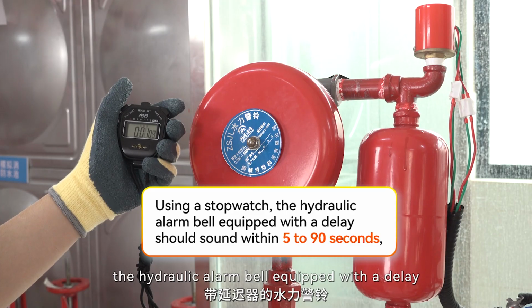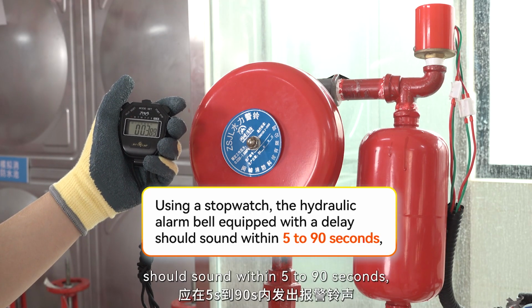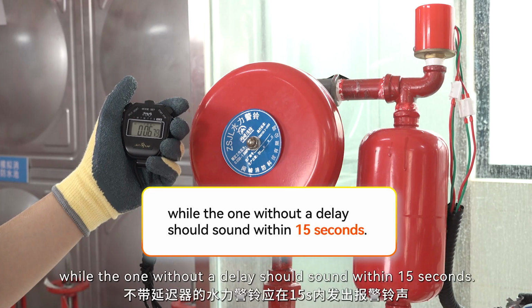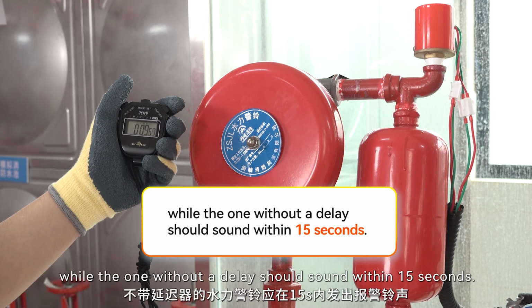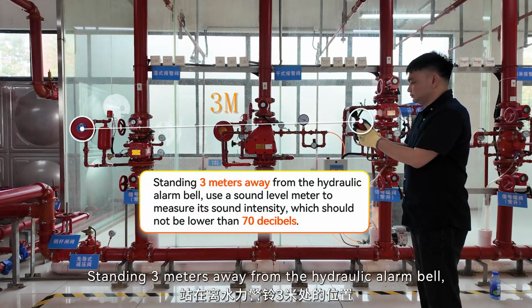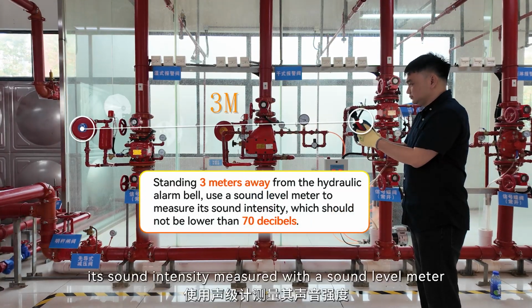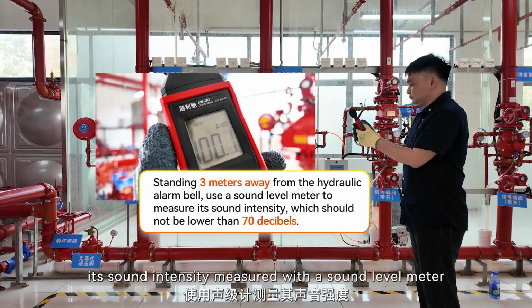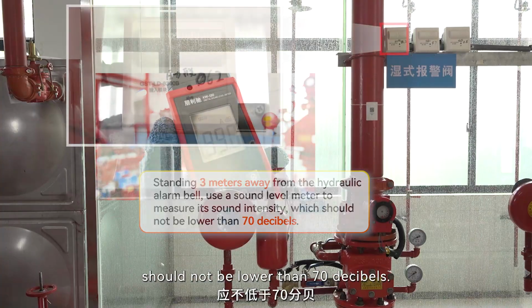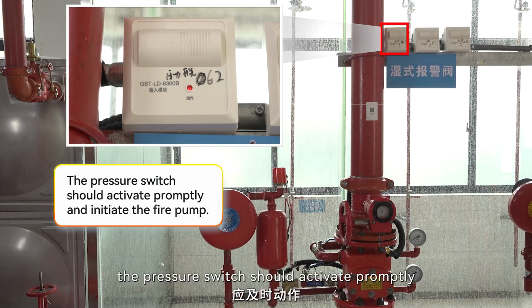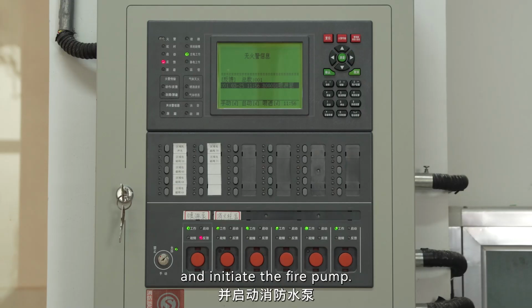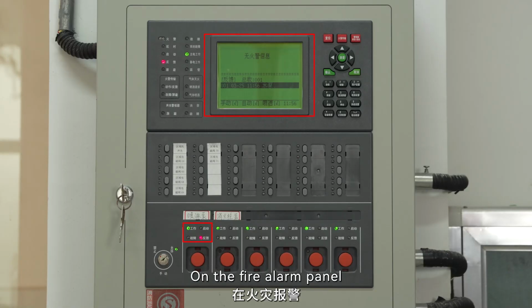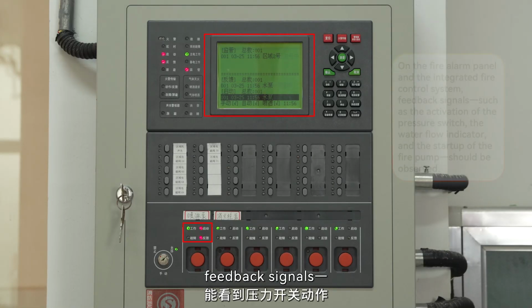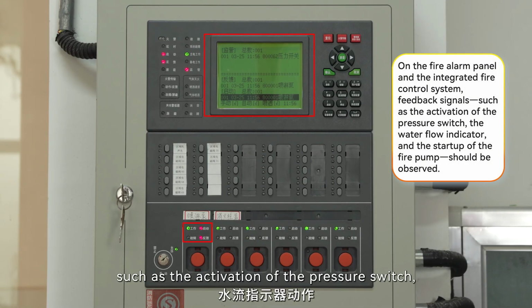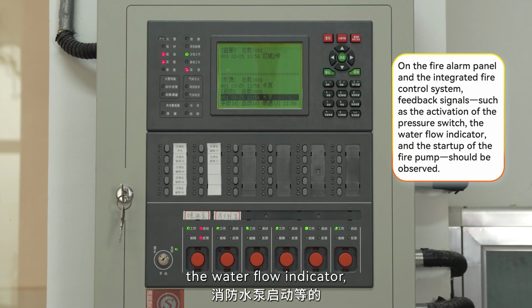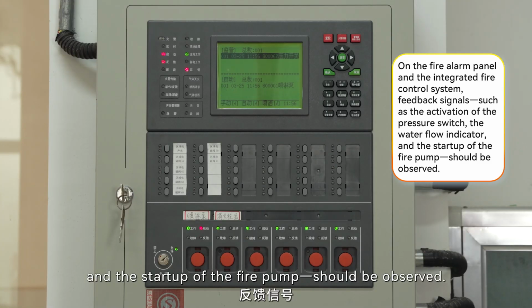Using a stopwatch, the hydraulic alarm bell equipped with a delay should sound within 5 to 90 seconds, while the one without a delay should sound within 15 seconds. Standing 3 meters away from the hydraulic alarm bell, its sound intensity measured with a sound level meter should not be lower than 70 decibels. Simultaneously, the pressure switch should activate promptly and initiate the fire pump. On the fire alarm panel and the integrated fire control system, feedback signals, such as the activation of the pressure switch, the water flow indicator, and the startup of the fire pump, should be observed.